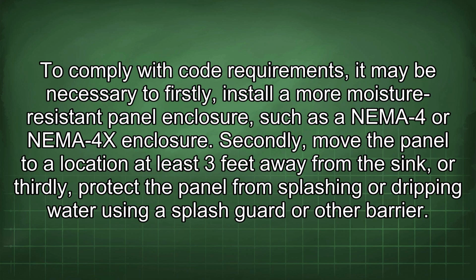To comply with code requirements, it may be necessary to firstly install a more moisture-resistant panel enclosure, such as a NEMA 4 or NEMA 4X enclosure. Secondly, move the panel to a location at least 3 feet away from the sink. Or thirdly, protect the panel from splashing or dripping water using a splash guard or other barrier.